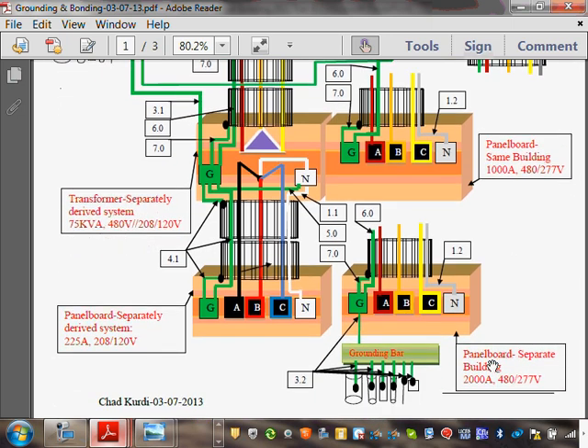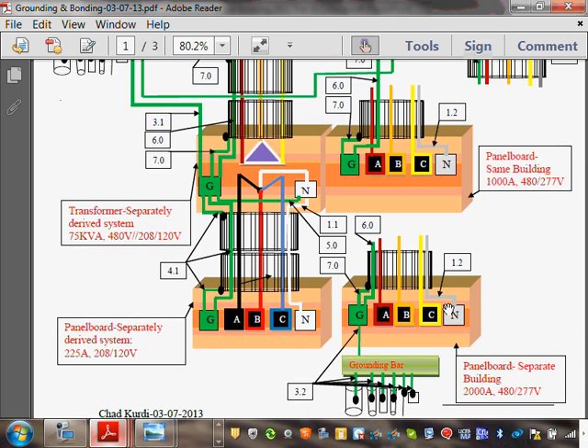Why a separate building? Because that captures grounding and bonding at a separate building. It has its own requirement. So a third building, so 3 feeders. And I picked these 3 feeders because these are the 3 scenarios that you're going to encounter. I would say 95% of the time you are encountering these 3 scenarios, right? Is there any other scenario, unless you deal with higher voltages? These are the scenarios you're going to be doing.